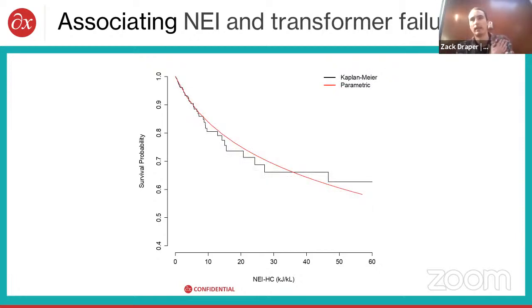So that meant we essentially combined those two data sets to create a single model. Every stair step in the Kaplan-Meier curve there is another transformer failing. We fit a smooth model to this curve to create a model we can use for all transformers, so we can measure what the NEIHC is for any given transformer and compare it against this curve to see what we expect its survival probability to be.